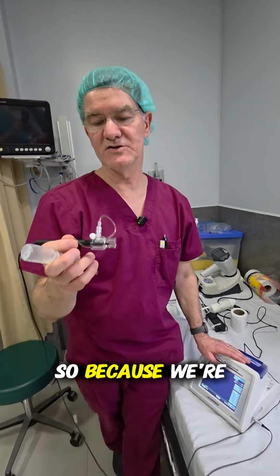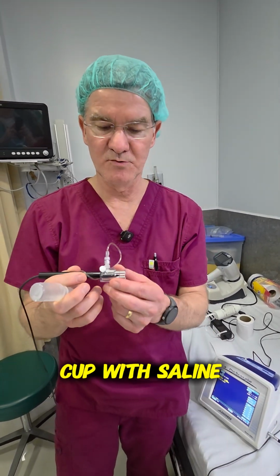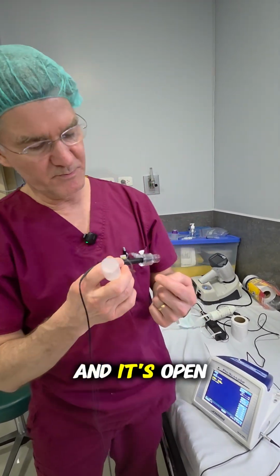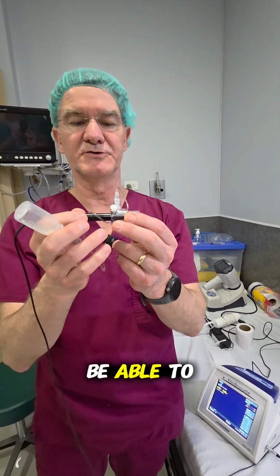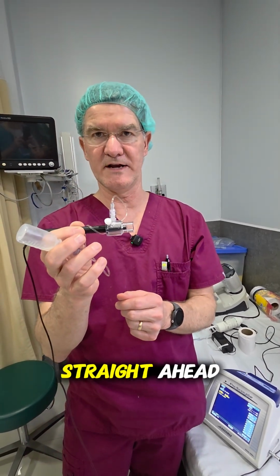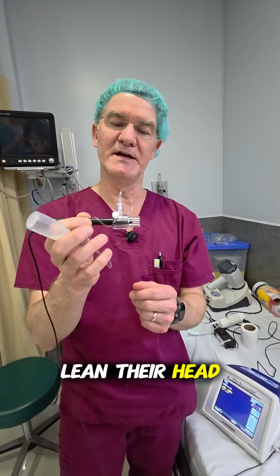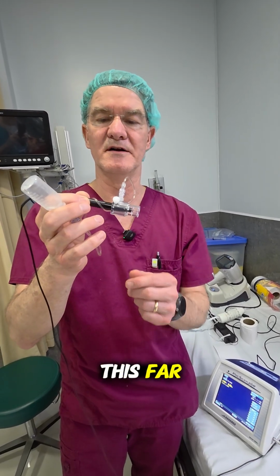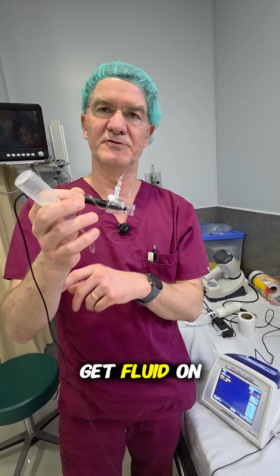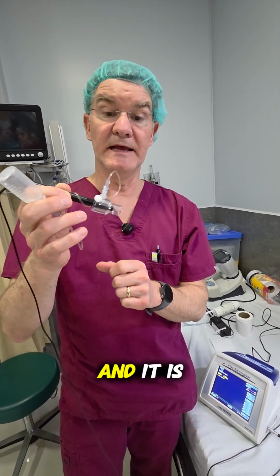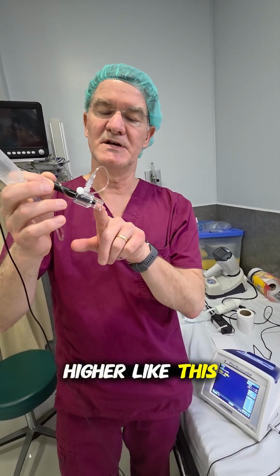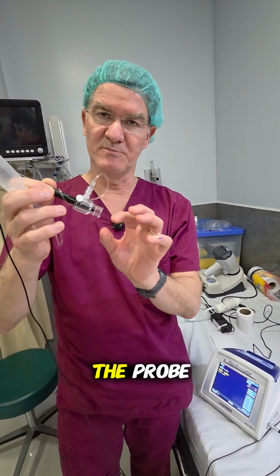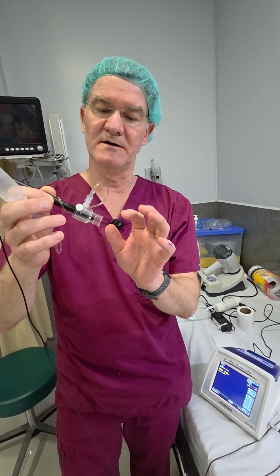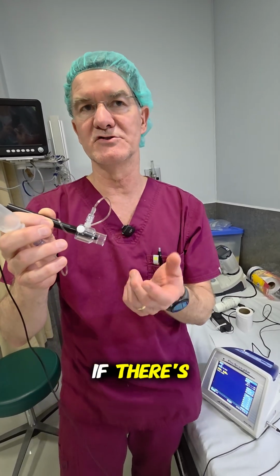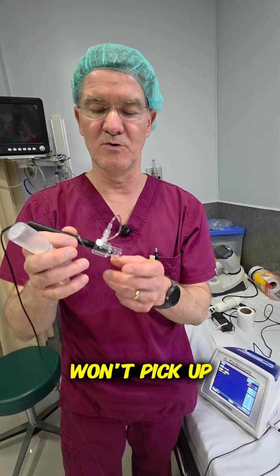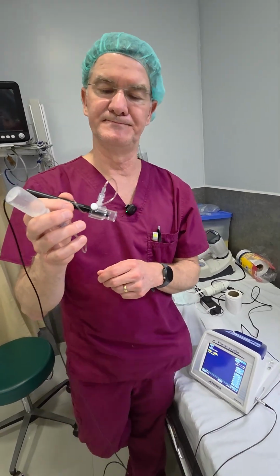So because we're going to fill this cup with saline, and it's open back here, you wouldn't really be able to have somebody look straight ahead. So what you do is just have them lean their head back slightly. You only need to be up this far, and then that's enough where you can get fluid on the end of the probe. And it is important to, maybe a little higher like this, but you do want the whole front face of the probe to be covered in fluid. That can be an error you can get if there's not enough fluid. It won't give you a good spike and it won't pick up a measurement.